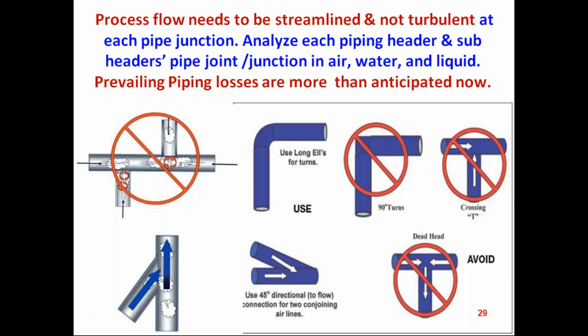If this is done in the compressor house and in the water piping and all the utilities, go for long bends and look for conjoining joints. This will reduce the end-to-end pressure drop or the flow drop in the flow process. All the end-to-end energy losses can be controlled by having a proper piping layout in the industry. This is a point to note. Not immediately will the industry do it, but we can suggest to the industry where the bottlenecks are.